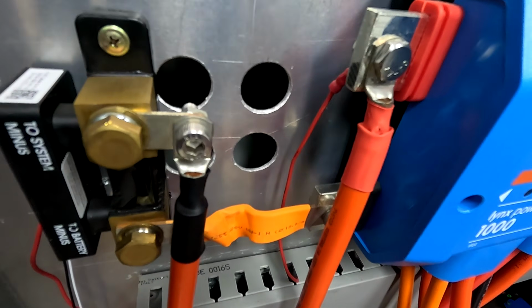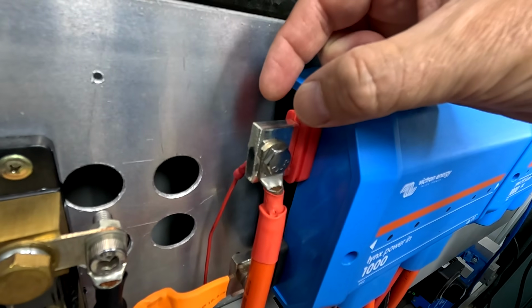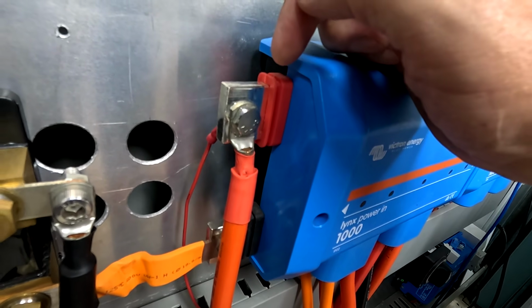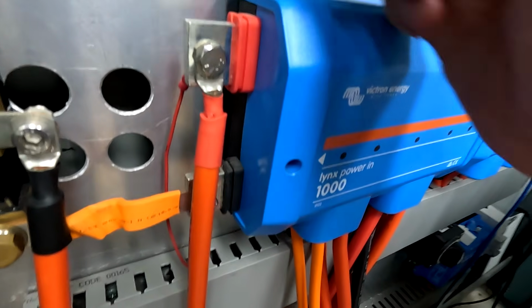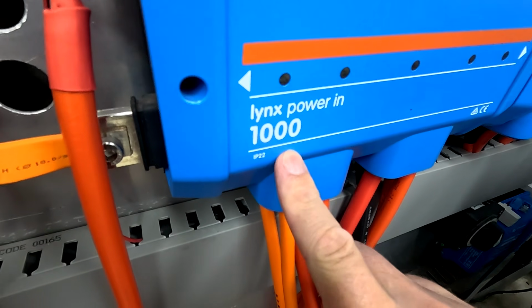Even the Victron Lynx bus bars, 300 by 7.8 thick, just give me close to 300 amps of ampacity, but certainly not 1000. Of course this all depends a bit on how the bus bars are installed, what insulation they have, and a few other factors which you sometimes can see in these tables. So when you look up the ampacity of these bus bars online, there's probably more confusion created than your questions being answered, but this is what everyone does. All these bus bars in these batteries, and even in the Victron Lynx system, are highly underrated.